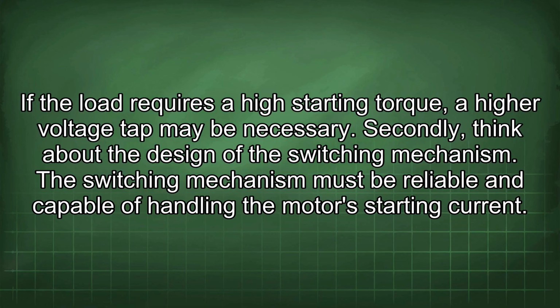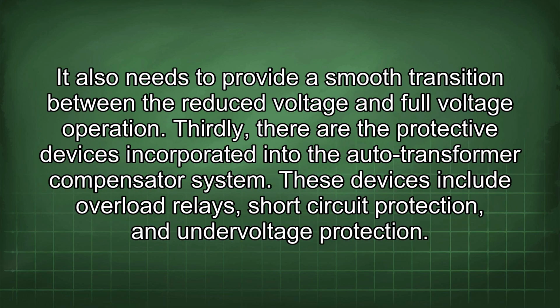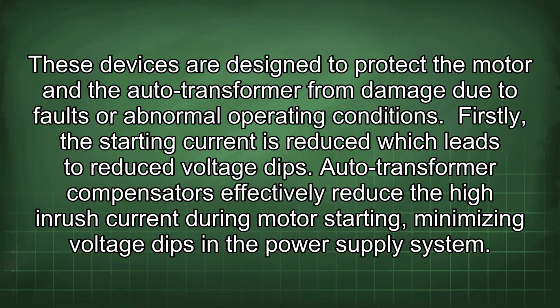Secondly, think about the design of the switching mechanism. The switching mechanism must be reliable and capable of handling the motor's starting current. It also needs to provide a smooth transition between the reduced voltage and full voltage operation. Thirdly, there are the protective devices incorporated into the auto-transformer compensator system. These devices include overload relays, short-circuit protection, and undervoltage protection. These devices are designed to protect the motor and the auto-transformer from damage due to faults or abnormal operating conditions.